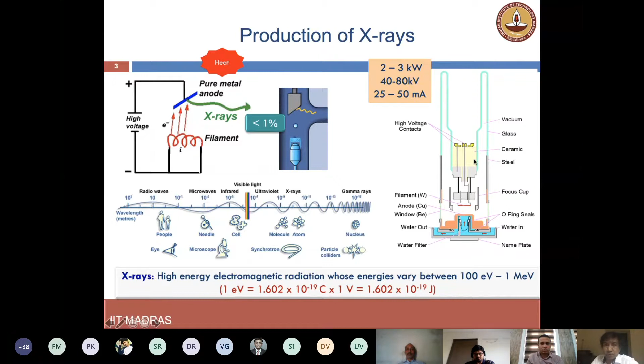So typically, we are talking of power in the range of 2 to 3 kilowatts, and we use voltage of around 40 to 80 kilovolts, around 25 to 50 milliamps to generate X-rays. You must know what kind of interactions typically happens when electrons are bombarded onto the target. So to get an idea of what kind of radiation comes.